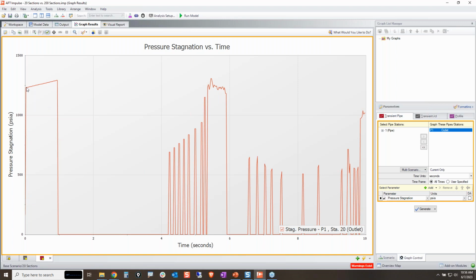Well, that's going to generate a really high surge pressure when you close that valve really quick. So we've got an initial pressure surge of about 1200 psia. Now, you do have a little bit of line packing as the pressure from the valve reflects and moves upstream, and then it drops. And then it starts causing all this madness.